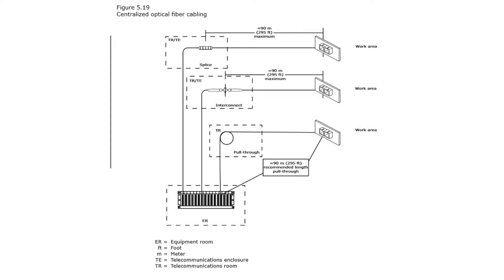But I thought we were limited to 90 meters or 295 feet for every type of cable in the horizontal distribution system. So how does this work? If you look at Figure 519 in your TDMM, you'll see three different scenarios. The first shows a pull-through in the TR and a total distance of 90 meters or 295 feet. The second shows the cable interconnecting in a TR and then extending another 295 feet or 90 meters. The third shows the cable splicing in a TR and then extending another 90 meters or 295 feet.